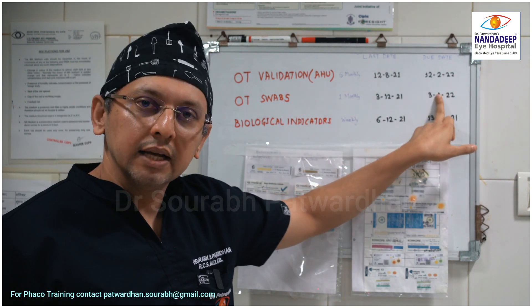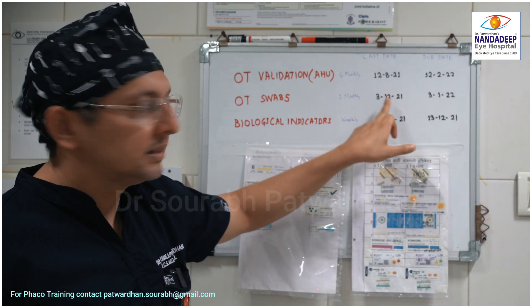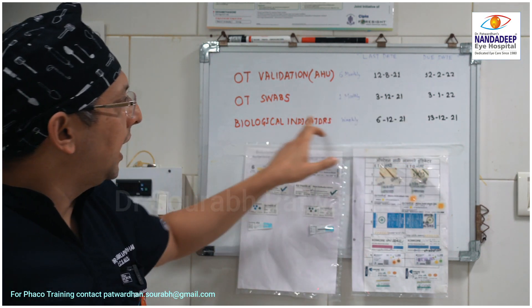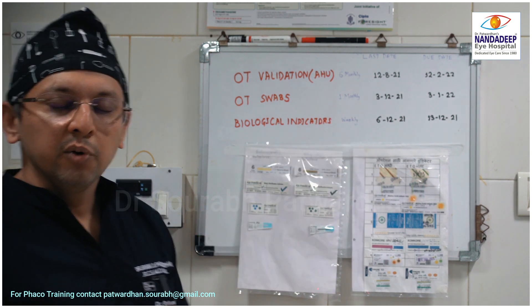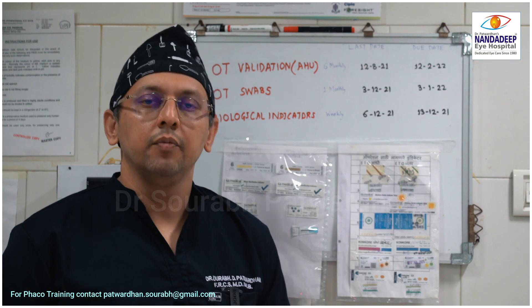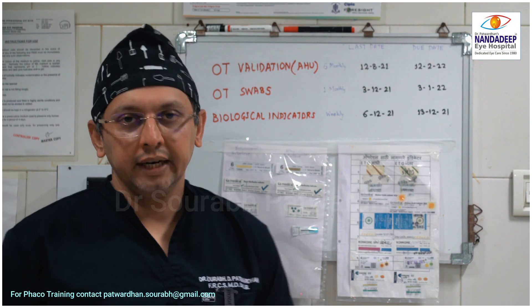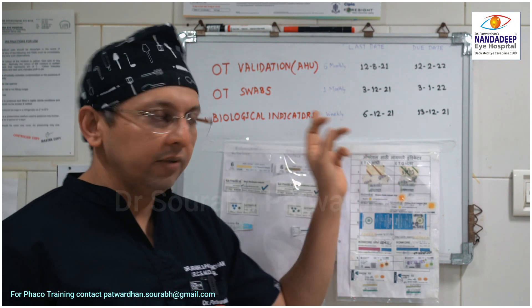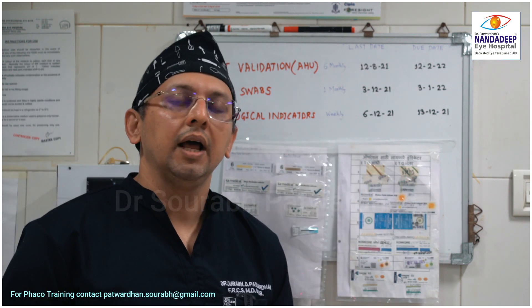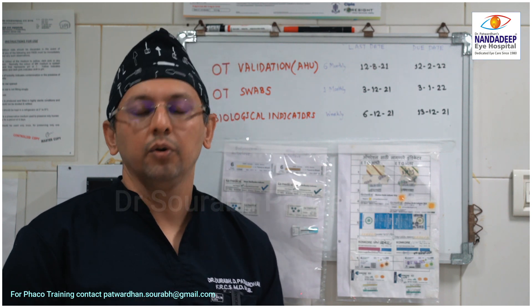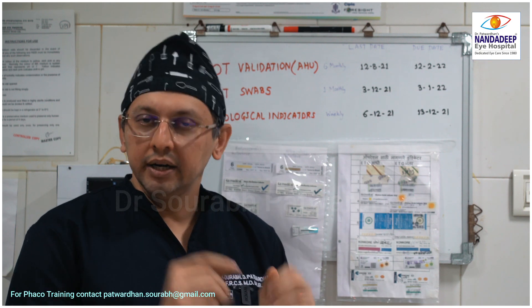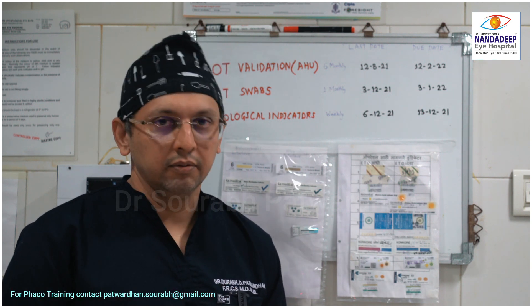The moment this due date has passed and the last date has not been changed, I know that it has not been done. Another important thing is the biological indicators, which are a must for each sterilization equipment. Every autoclave, every ETO machine or plasma sterilizer must have biological indicators checked every week. If they have failed, you should stop using that particular equipment and get it repaired so that it is safer for our patients.